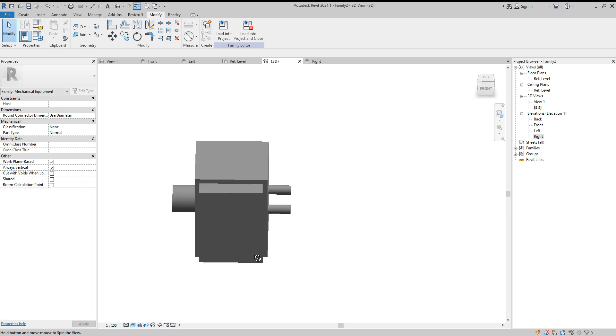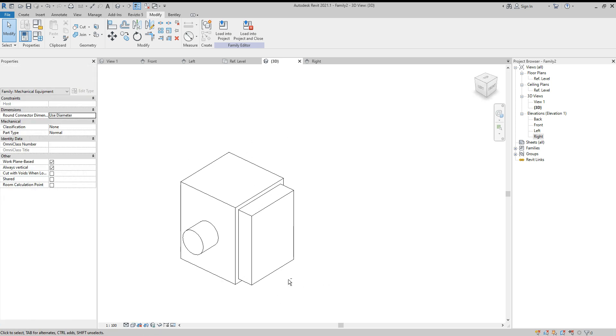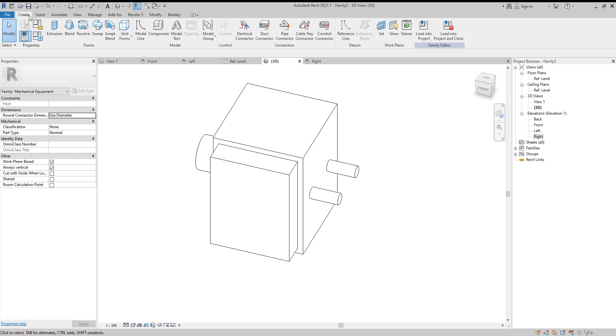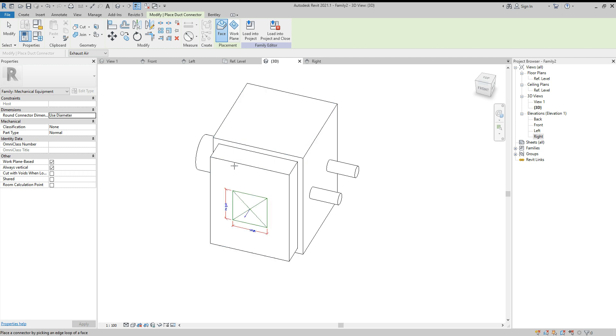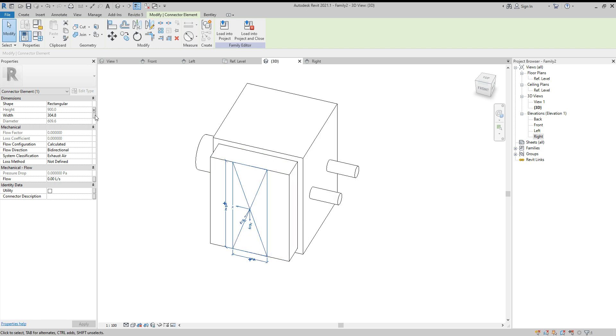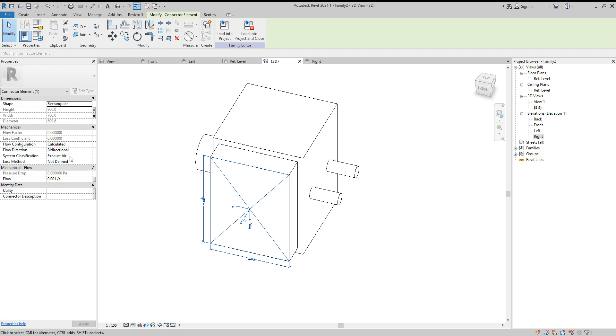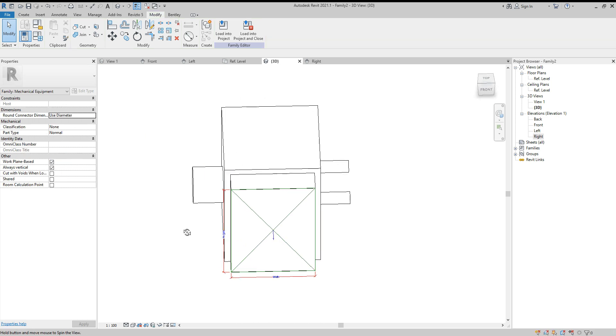Next step is to set connectors. Switch to Wireframe view. Go to Create, Duct Connector, select the rectangular duct face. Set the shape to Rectangular, set Height to 'Duct Height' parameter, and Width to 'Duct Width' parameter. The system classification can be set to Supply or Exhaust as required.